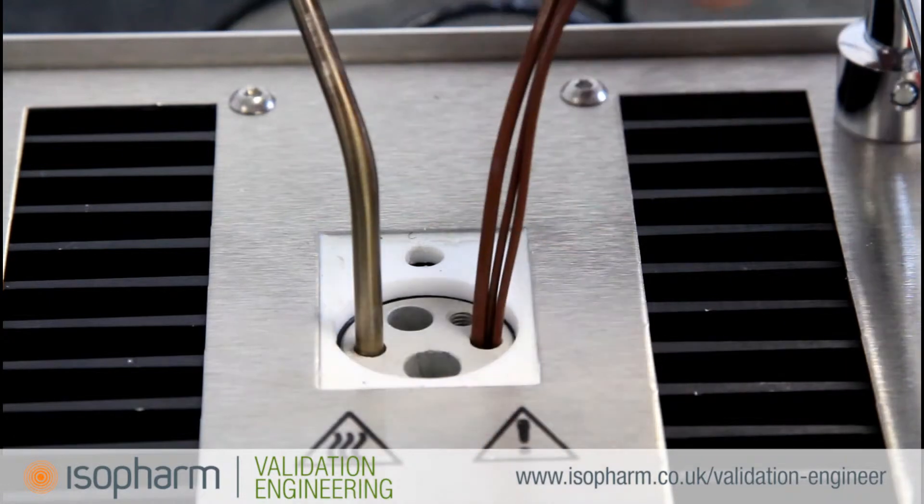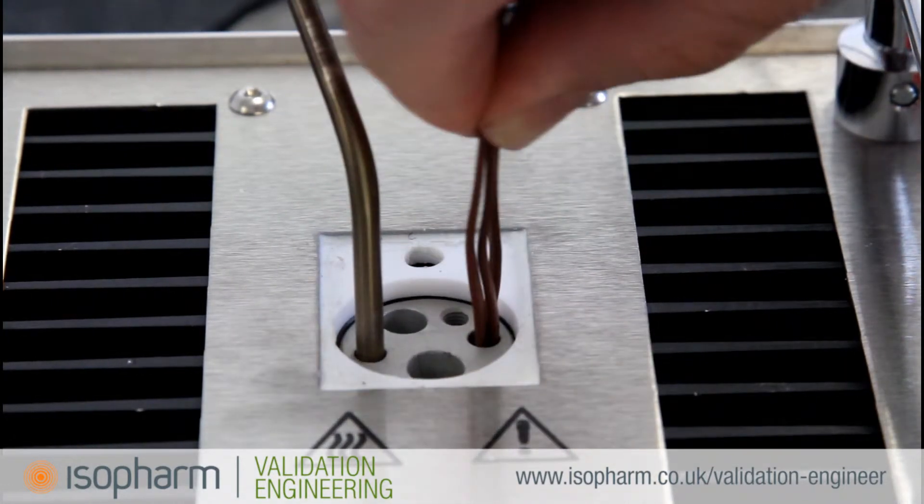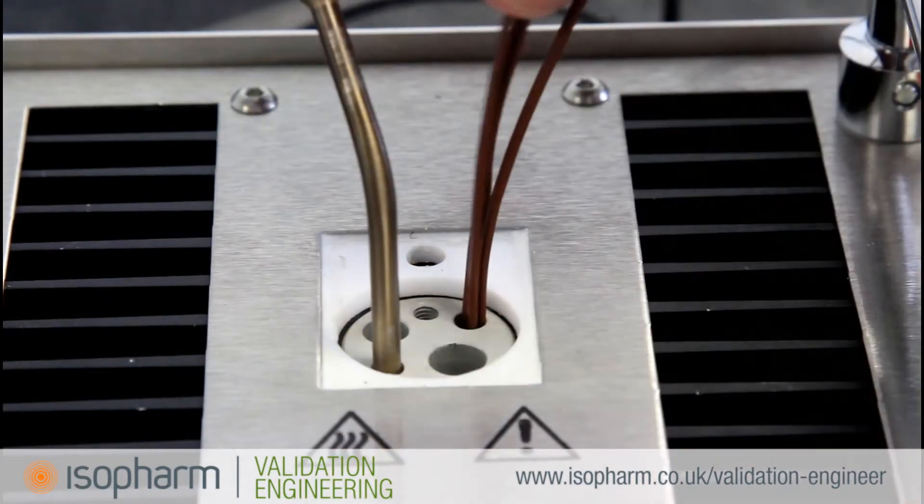If any thermocouples are positioned higher than the rest, calibration of that probe will be inaccurate. For more information on stem conduction and thermocouple theory, please see the technical section of the Isopharm website.